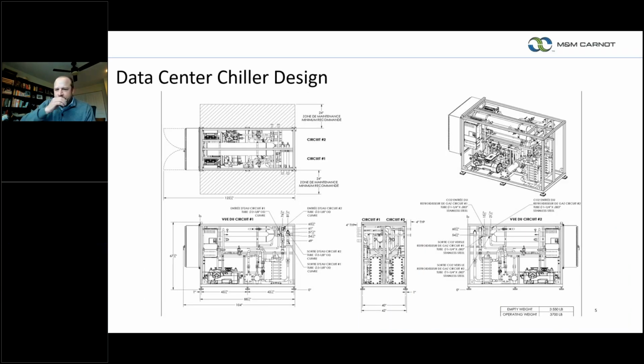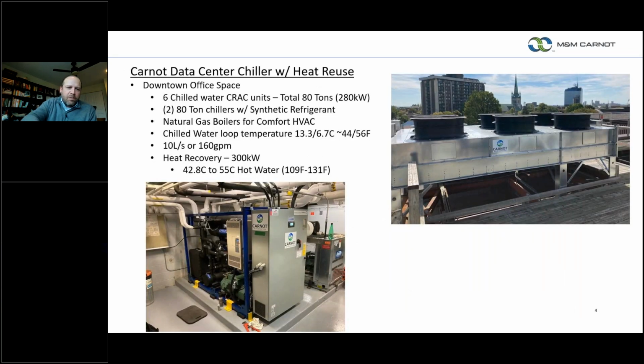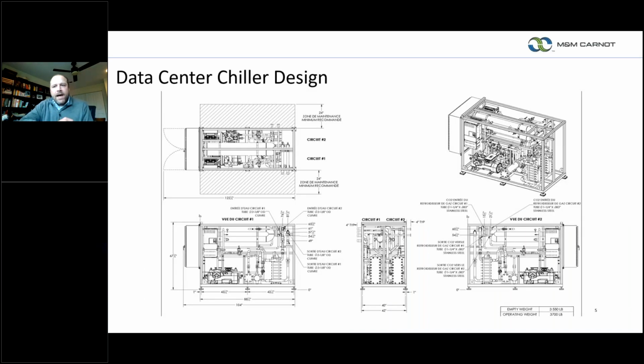So I showed a couple of pictures, and I'm missing one that I'm going to show you in a second. But on the left, this is our indoor unit. It's a dual circuited machine, so it has 2 compressors, 2 evaporators, 2 receivers, connected up to a dual circuit gas cooler, which is the picture on the right. That's on the roof. It's a pretty compact footprint, but this shows you that we have 2 circuits on this one machine, 40 tons per circuit, and the piping for each circuit is separate.